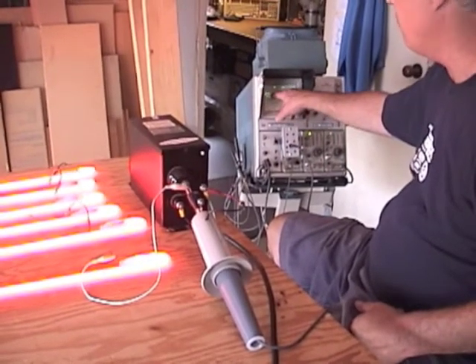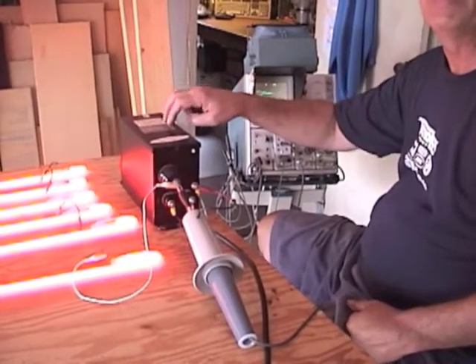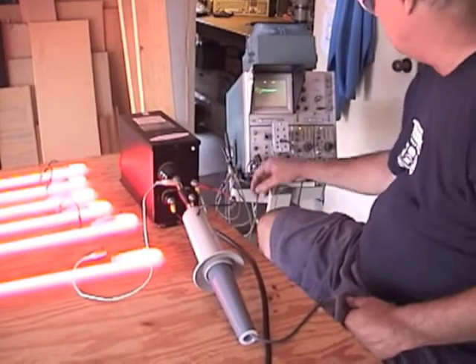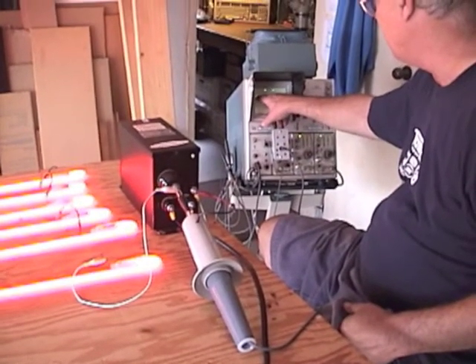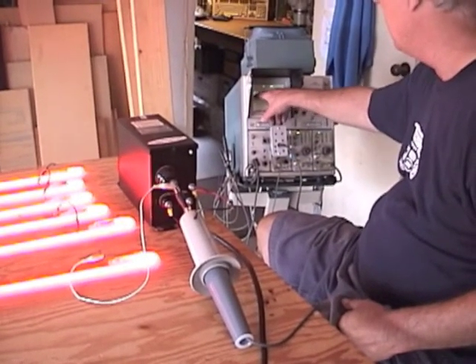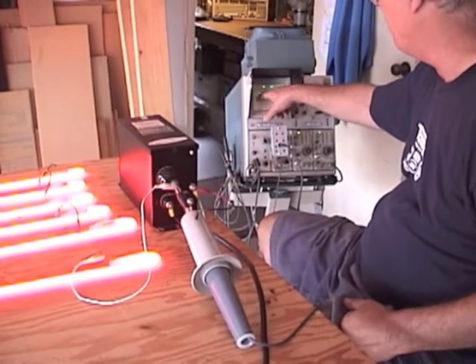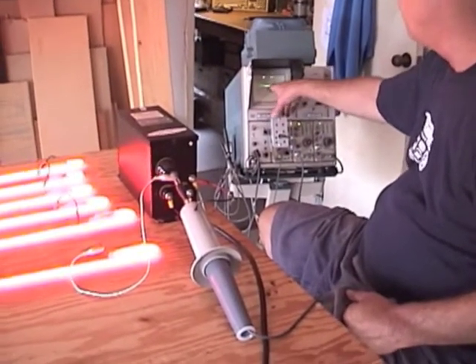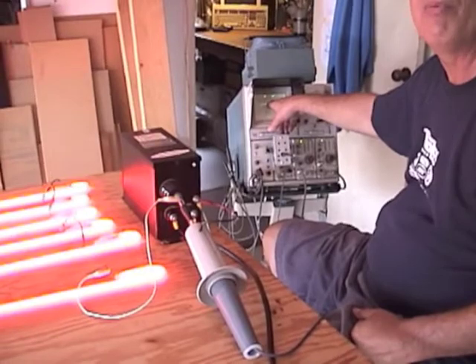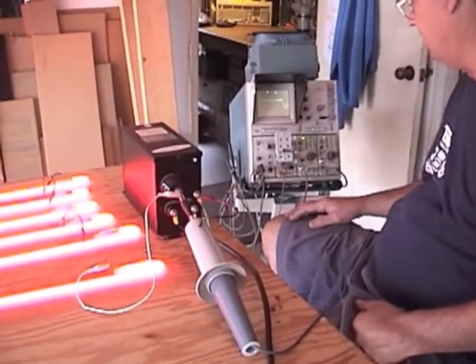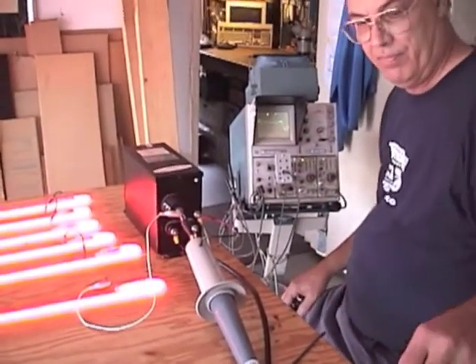Now, this ringing waveform is what kills the trannies. As you can see, it's not very significant on this one, but because it's ringing, you get voltage peaks above and below, so it adds to the normal operating voltage. Okay, that's all well and good.